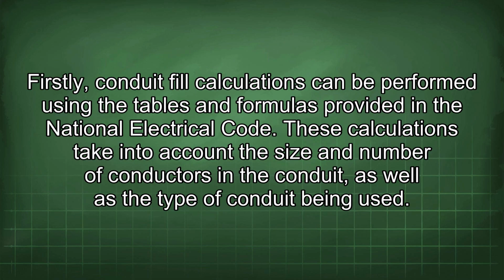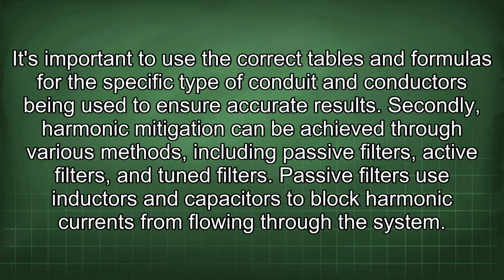Firstly, conduit fill calculations can be performed using the tables and formulas provided in the National Electrical Code. These calculations take into account the size and number of conductors in the conduit, as well as the type of conduit being used. It's important to use the correct tables and formulas for the specific type of conduit and conductors being used to ensure accurate results.